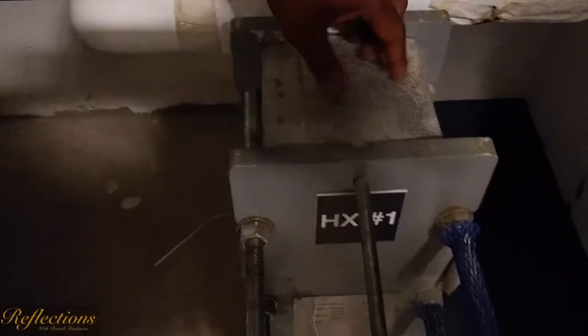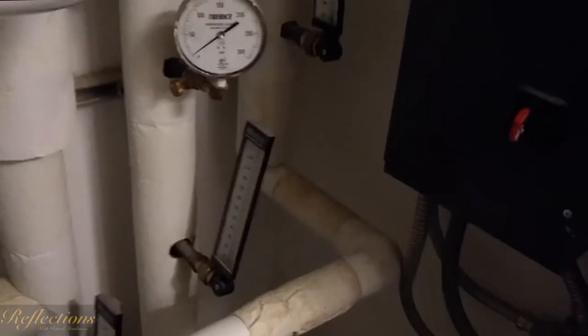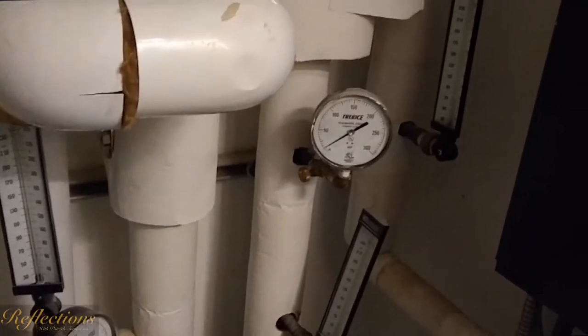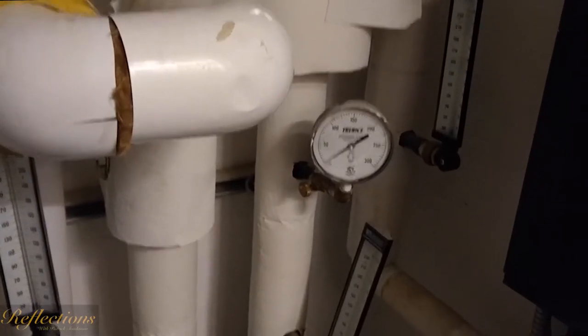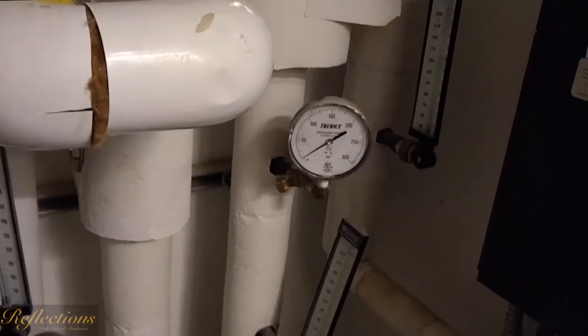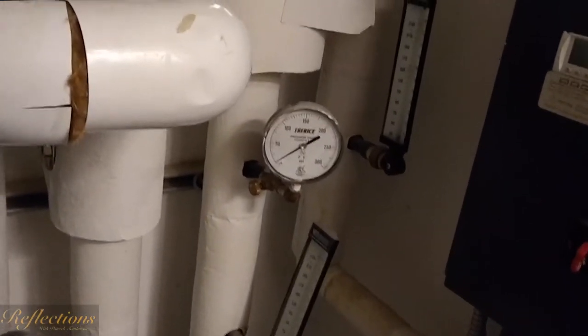The water goes into the heat exchanger, cooling down the plates in the heat exchanger, and then going right back into the well. We pull the water out of the well at approximately 55 degrees, and when we send it back down into the well, it's probably no more than 70 degrees.